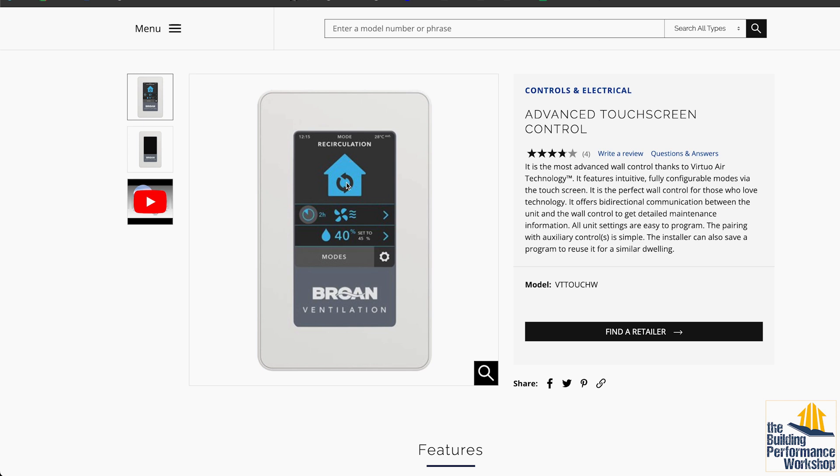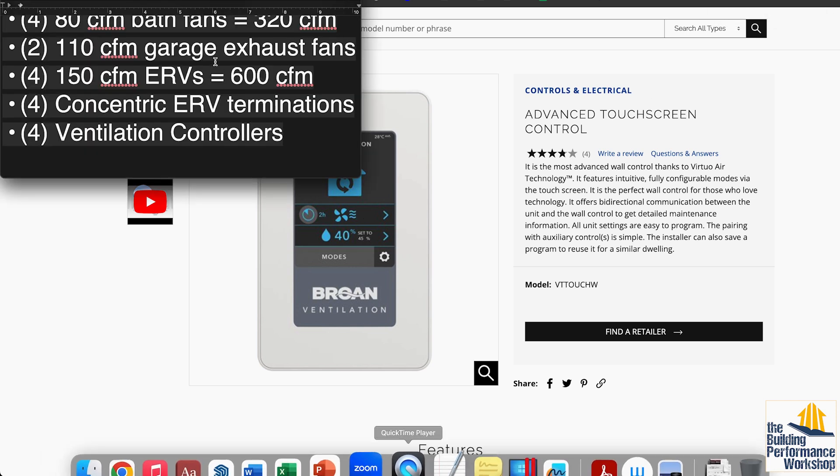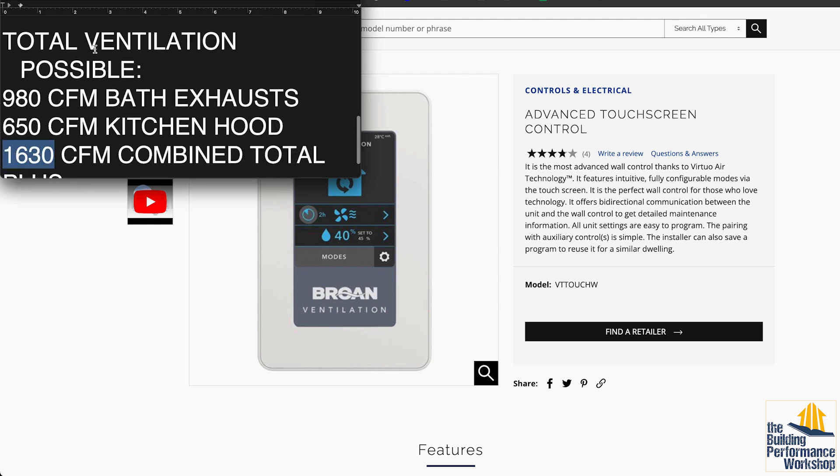I will say that this is interesting. The fact that they screenshot on the recirc mode. This is something that Broan ERVs and a few other ERVs can do, which is actually against code in some places. It means that they close off the damper of the outgoing air and they actually have the outgoing air, the stale air, turned around and come back into the house. I think it's so that you can kind of build some more energy efficiency into it and potentially also defrost the core. I think that there might be some other things in it, but I would just say in general in my practice I'm only recommending ERVs if you're going to use them as bath exhaust because you can't use bath fans anymore, in which case you would never want to do this. That would be a total disaster.